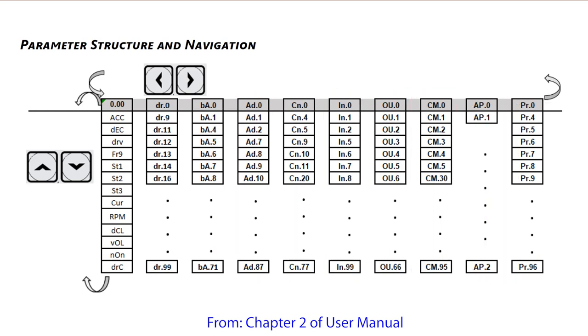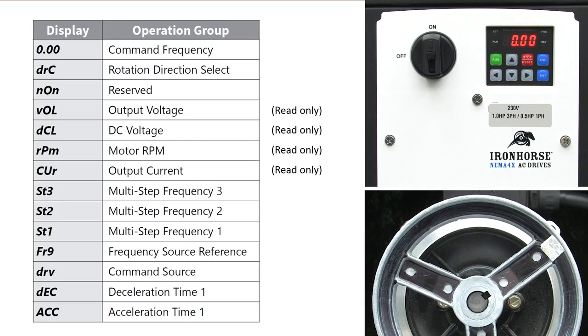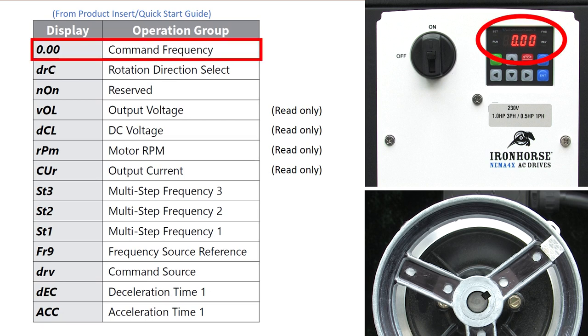For this video all we need is the acceleration, deceleration, drive command source, frequency source and forward reverse direction control so we only need this top level operations group of parameters which we access using just the up down arrow keys. This chart showing that operations group of parameters, which I stole from the product insert that comes with the drive, will help us keep track of where we are. The drive is currently showing us the frequency display so we are here on the chart.